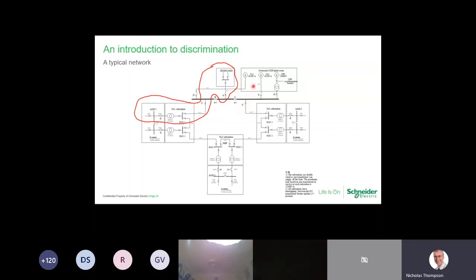One thing to highlight here: when we've got high voltage or medium voltage generators directly connected onto the switchboard through a circuit breaker, that could potentially increase the fault level over and above what the equipment is rated for.